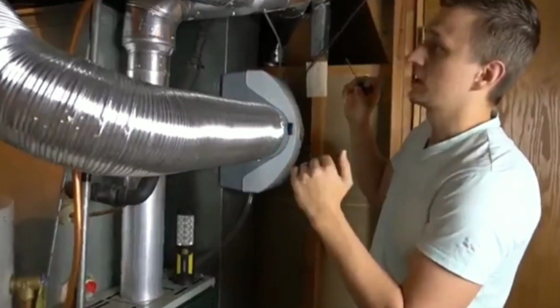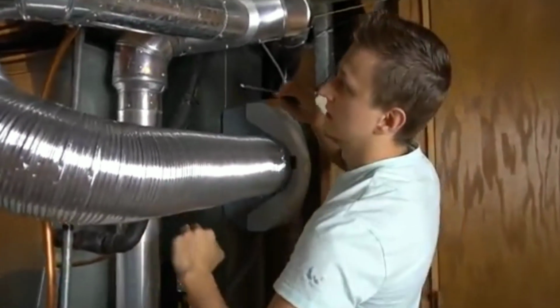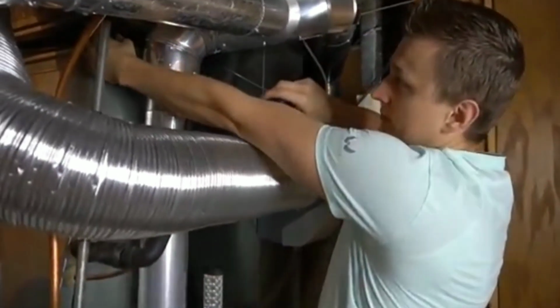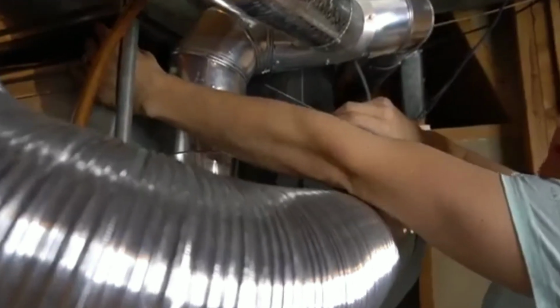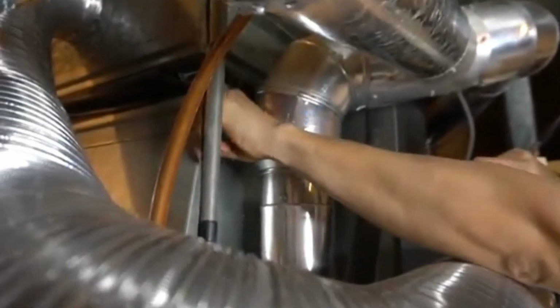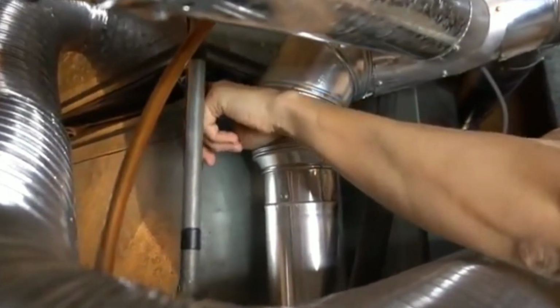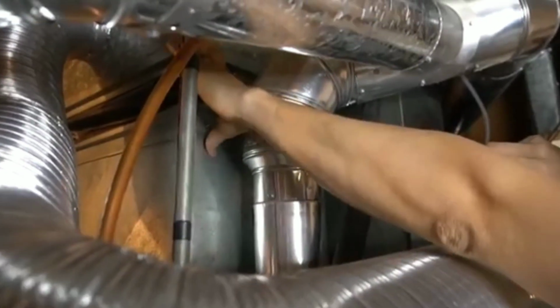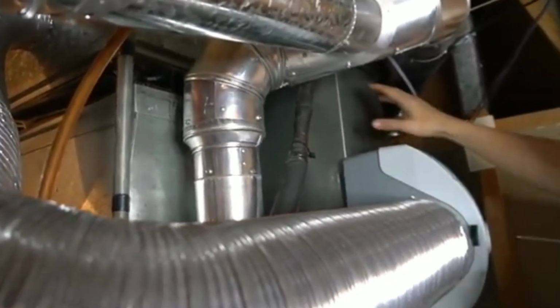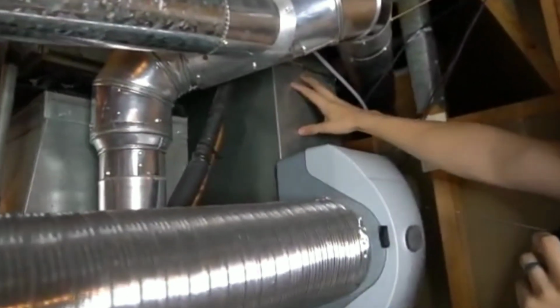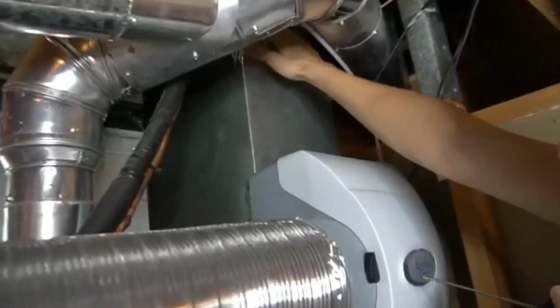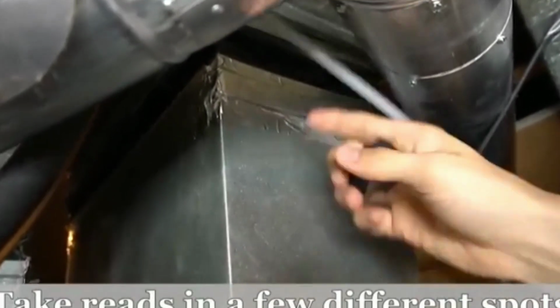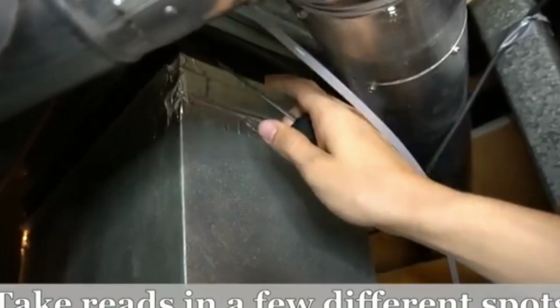An easy way to check the temperatures will be in these canvases. Most furnaces in the ductwork, you'll have this black canvas on top of your furnace. Basically, this is my supply. And one in the return duct, right here. This black piece right here, the canvas. And you can just poke your poke-in thermometer right in there to measure the temperatures.